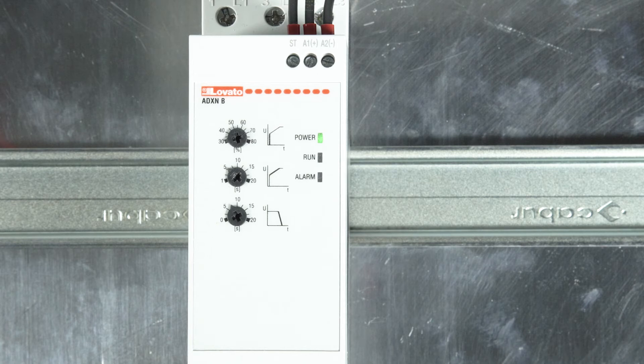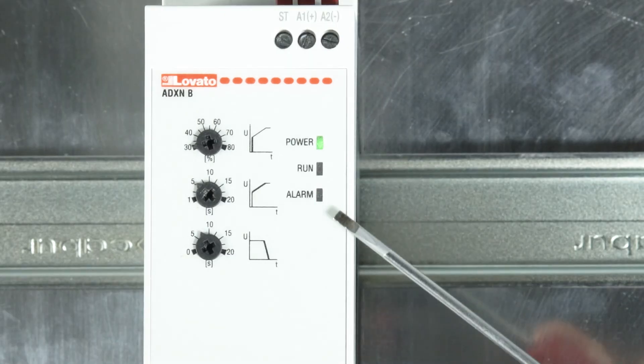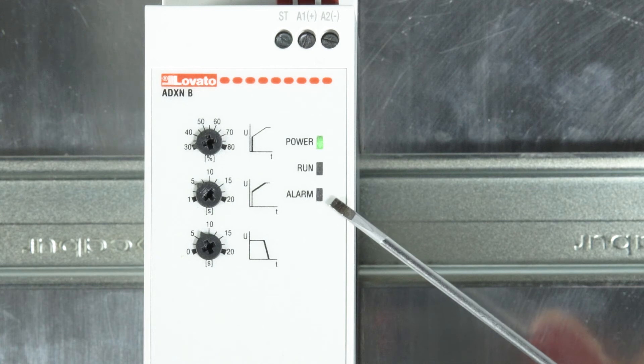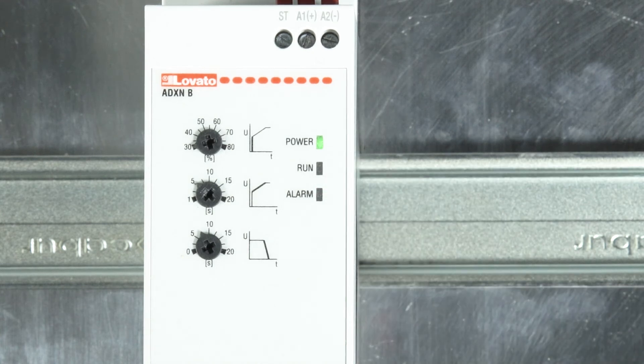For example, in this case, we can see three consecutive blinks of the alarm LED, followed by a brief pause, which indicates alarm A03: wrong phase sequence.